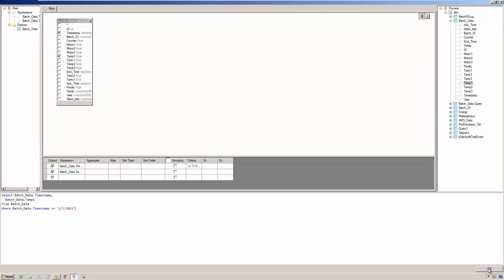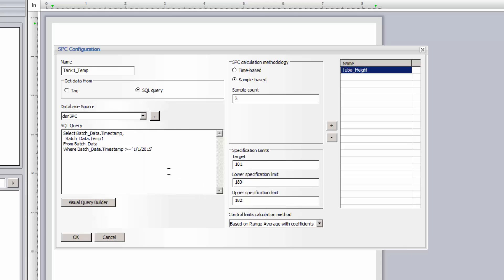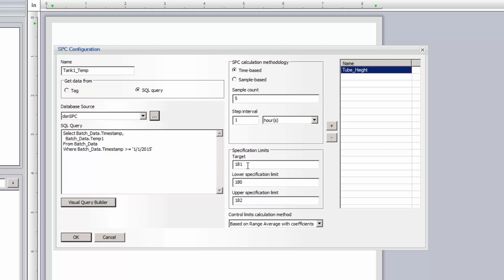With the query built, I'll specify time-based as the SPC calculation methodology. I'll use the first five measurements for every one hour. If you wanted, for instance, six measurements per hour, but spaced at 10-minute intervals, you could create a sample-based 10-minute aggregated data filter, or ADF, on the raw data to get the 10-minute subintervals. Let me quickly set up the target and limit values for this configuration, and the control limit calculation method, and add this configuration to the list. Note that the target and limit values do not need to be hard-coded. By double-clicking in each field, you can then reference a report object that contains this specific limit value.